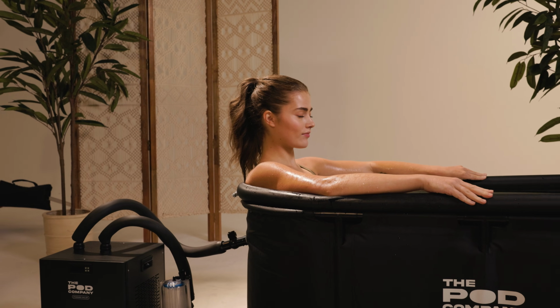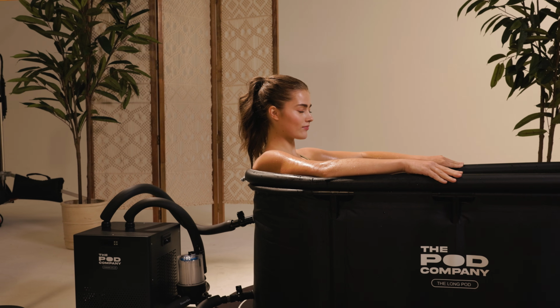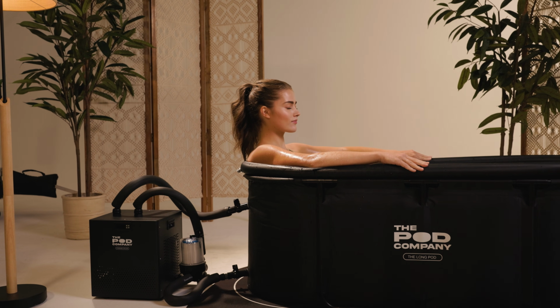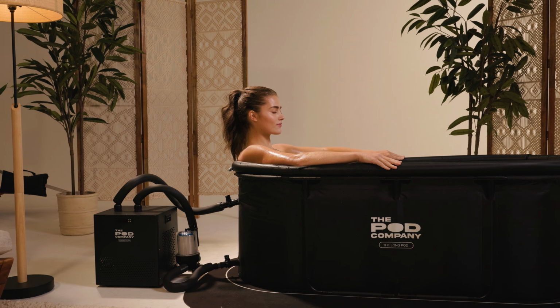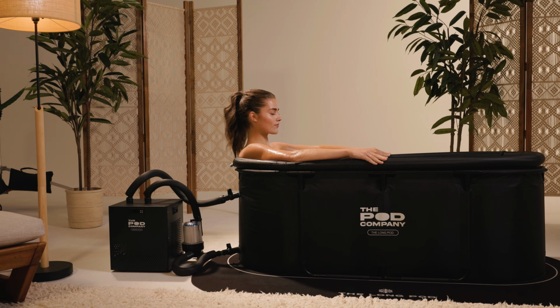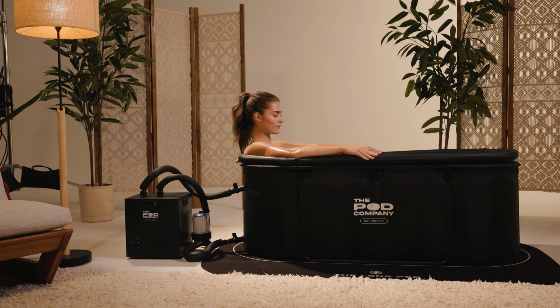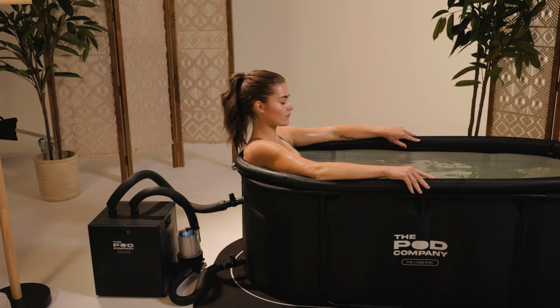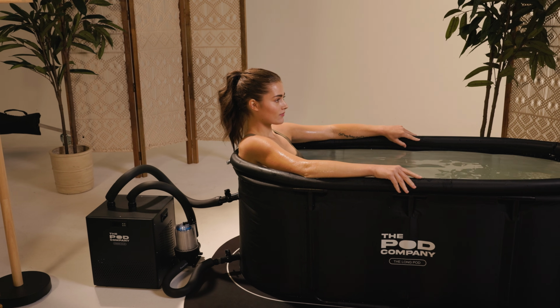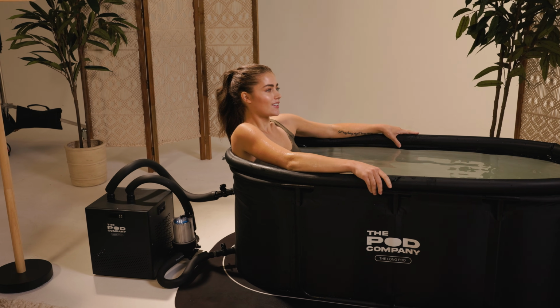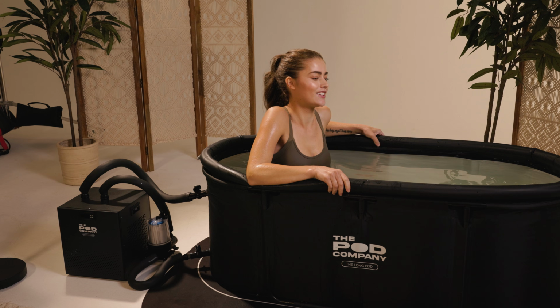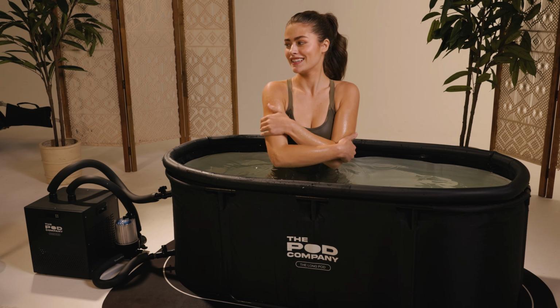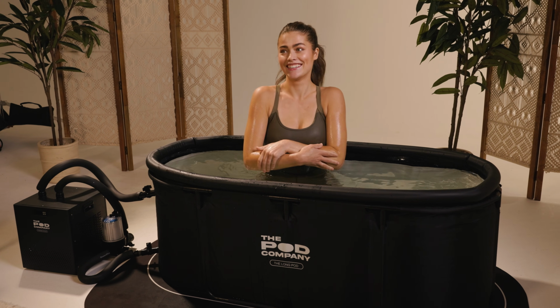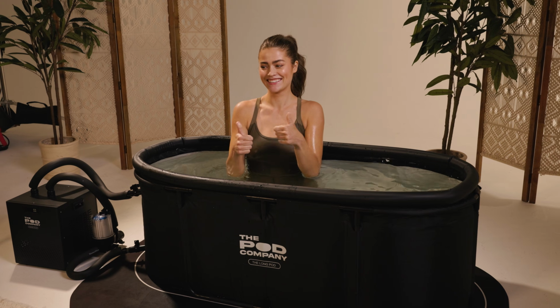The chiller will now show the current water temperature and will begin cooling down to the set temperature. You should hear the chiller's compressor start after around 2 to 5 minutes. Please allow 1 hour for the temperature to start dropping as the chiller requires some time to start cooling. Depending on the initial water temperature, your chiller version, and how hot it is where you live, the water should be at the set temperature within 5 to 15 hours.